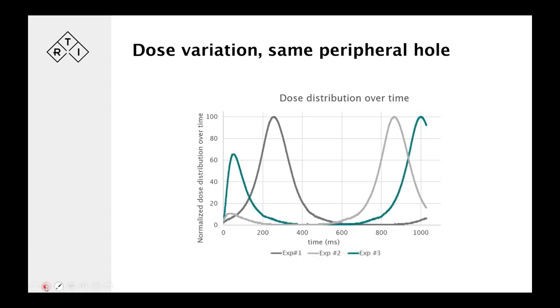And here is this third one, where we have a double peak on it, which is kind of odd. Now, this tells us that the tube starts to fire in different positions. And you may think that, well, maybe that doesn't do very much. Maybe it evens itself out because it's a circular motion.